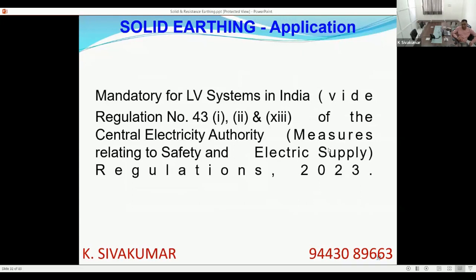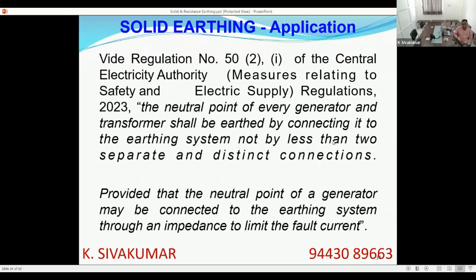So, application: the recently released CEA regulation 2023. If you read regulation 43, sub-regulations 1, 2 and 13, it is mentioned that the neutrals of every generator and transformer must be connected to the nearest earth electrode or earth connection, earth grid, by not less than 2 separate and distinct connections. Since there is no mention of the word impedance, it implies that they have to be connected solidly. This is for voltages more than 650 volt, that is, high voltage systems. The same CEA rule 50 says that the neutral point of every generator and transformer shall be earthed by connecting it to the earthing system by not less than 2 separate and distinct connections.